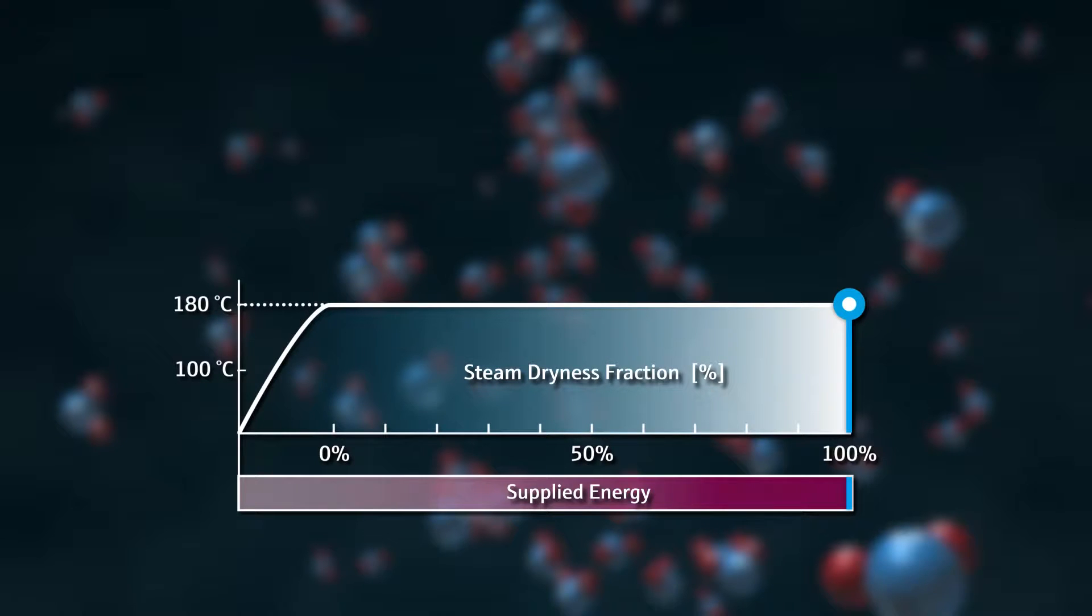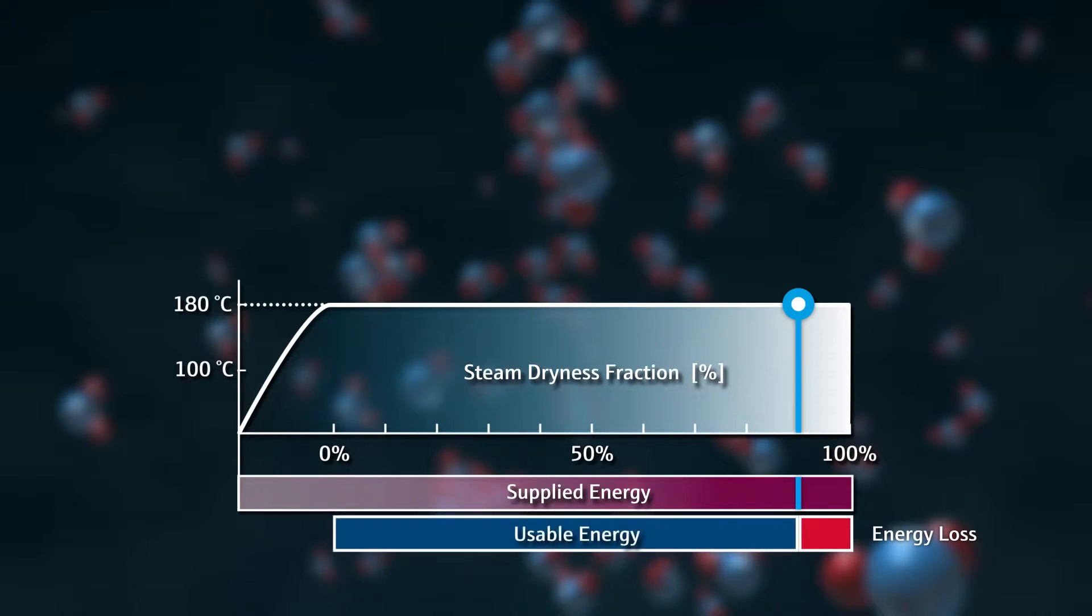The dryness fraction of the steam thus determines the energy content directly usable. If, for example, steam is only 90% dry, in other words contains 10% liquid water or condensate, then its usable energy amounts to only 90% and has therefore less value.